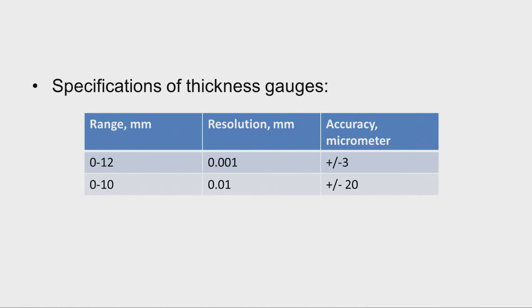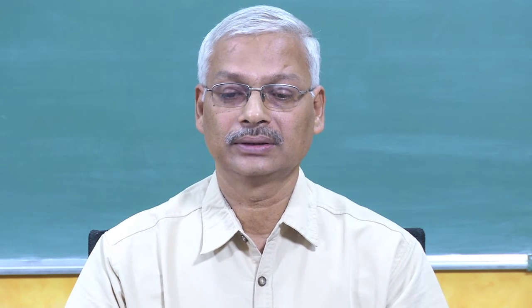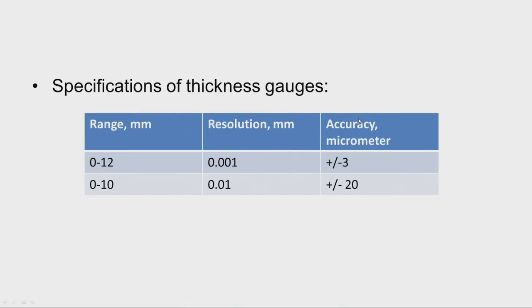Specifications of thickness gauges: available in ranges of 0 to 12 mm and 0 to 10 mm, with resolutions of 0.001 mm and 0.01 mm, offering accuracy of plus or minus 3 microns to plus or minus 20 microns. Depending on our requirement, we select and use the appropriate instrument.